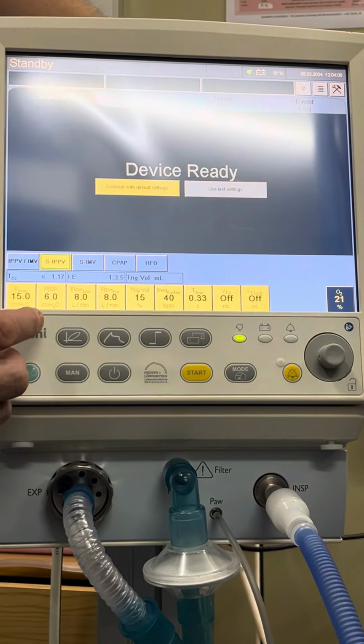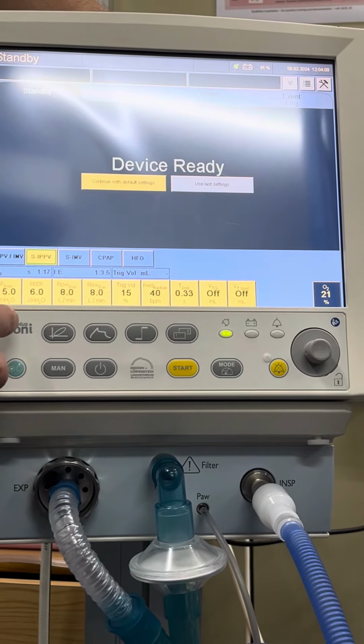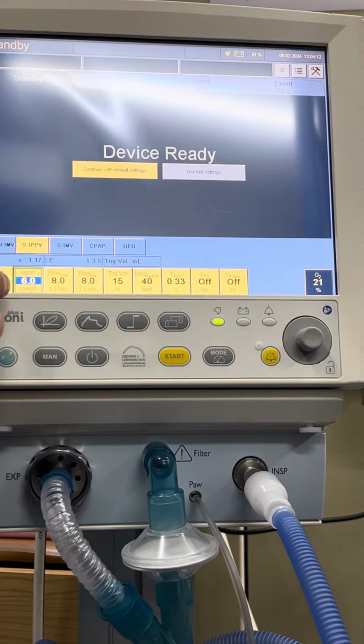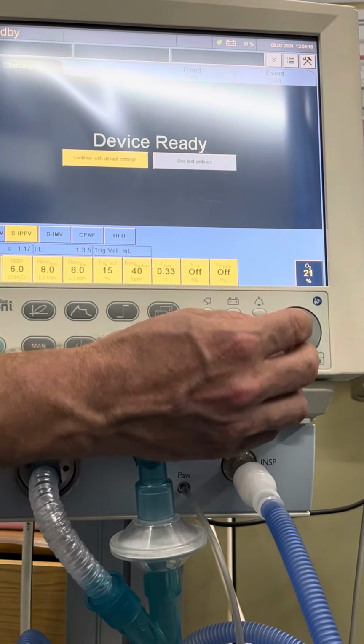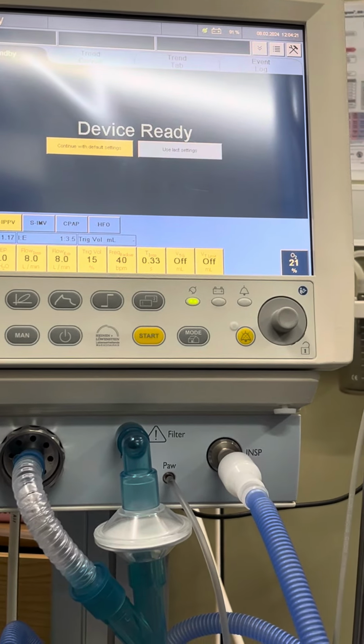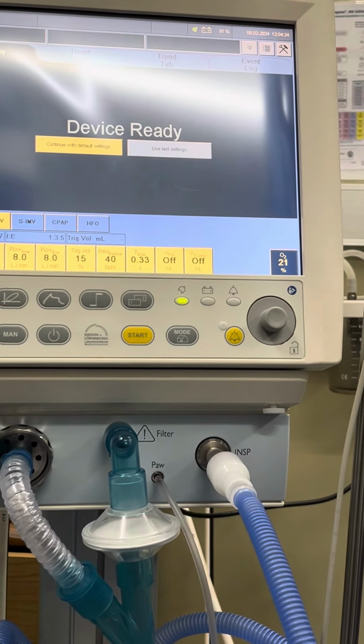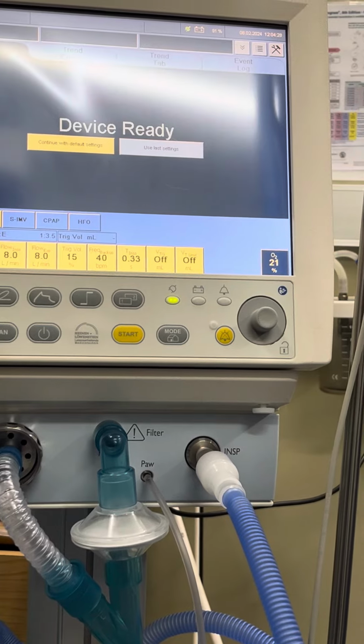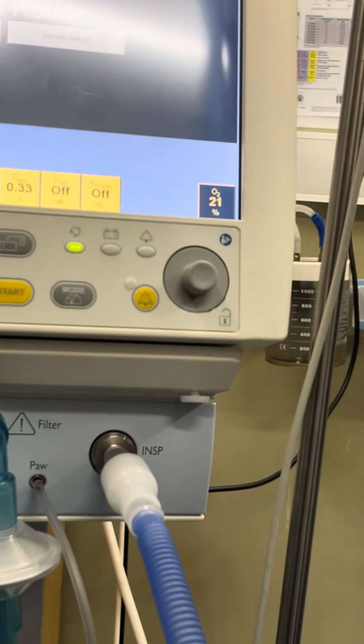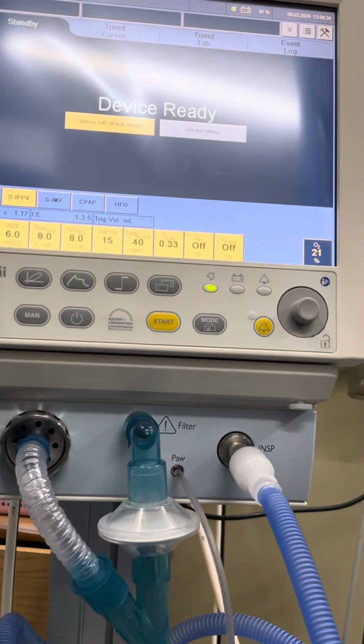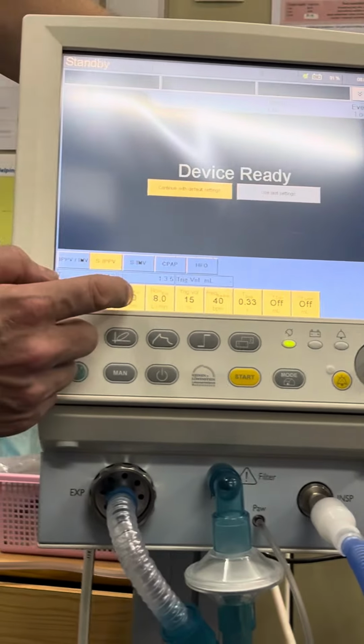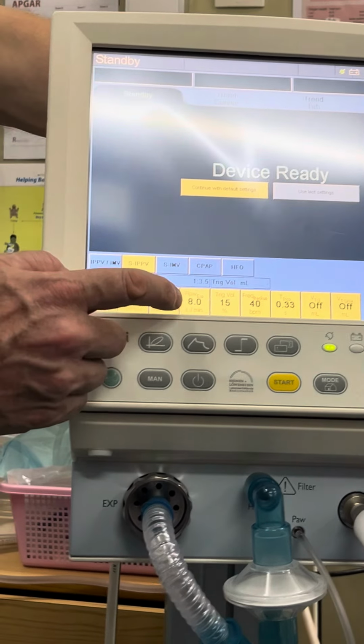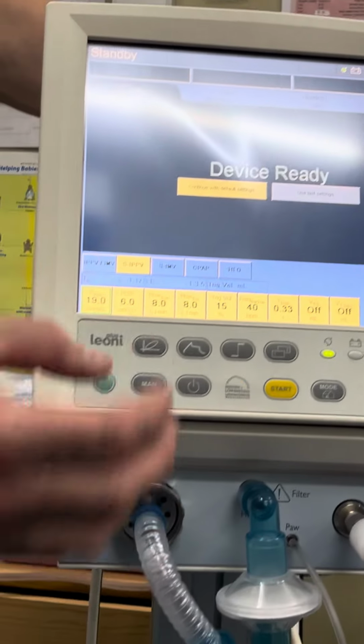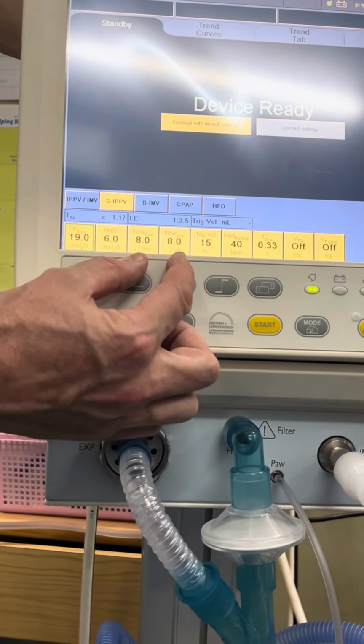And we have the PEEP of 6. Let's keep it there. Inspiratory pressure, let's put it on 19. 20 is average, 23 is much, 17 is not much. So this one is the PIP, right? That's the PIP, correct. Inspiratory pressure. And the flow, there's one inspiratory flow, one expiratory flow. They're both on 8 liters. That's okay. Don't make too much out of this. As long as the flow is on 8 to 10 liters, it's okay.